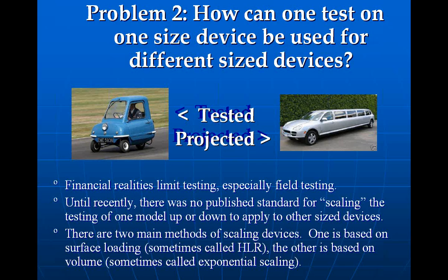In fact, there was a sweet spot. We found out the sweet spot was around 24, 25 for my device, gallons per minute per square foot. And that's kind of what we've decided we designed to. In all jurisdictions, we're generally under 20 anyway, based on some other things. The high flow, because we're a stay online, can change that. But HLRs is the way we went.